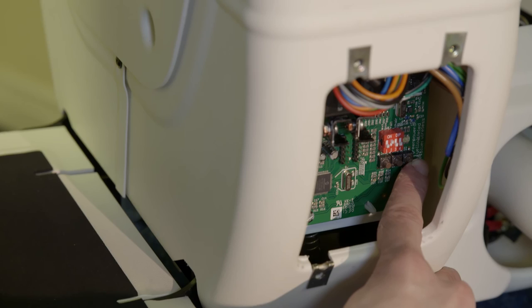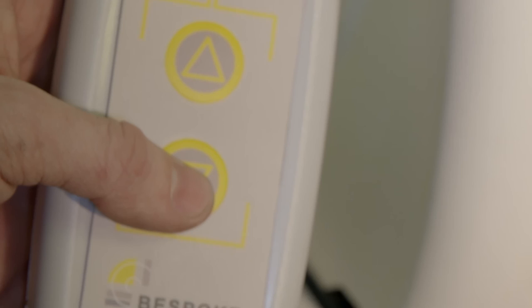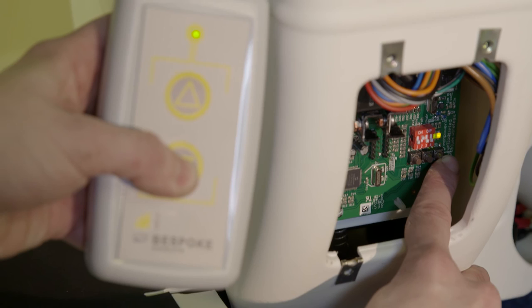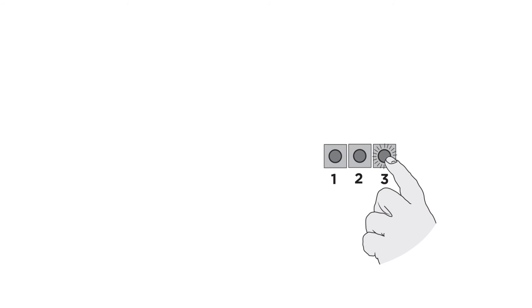First, turn on the lift. Next, hold microswitch 3 until the LED stops flashing, then release. Now press either button on the remote until the PCB LED flashes. Your first remote is now fully linked.